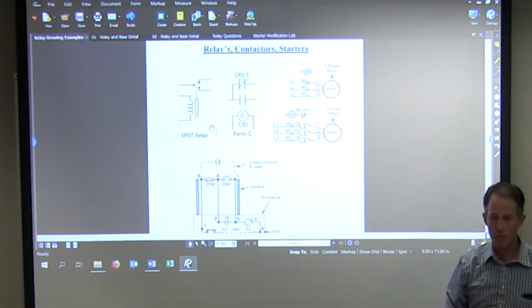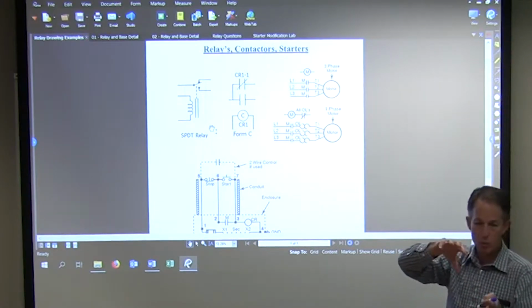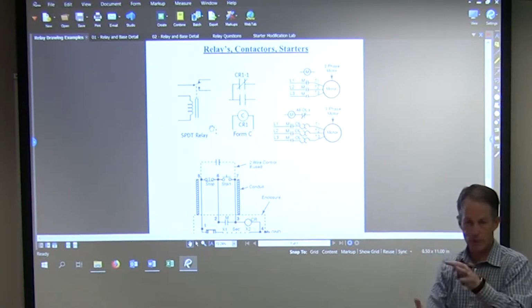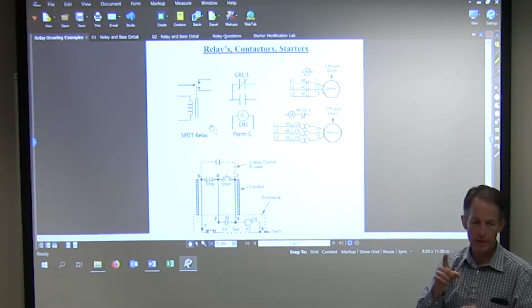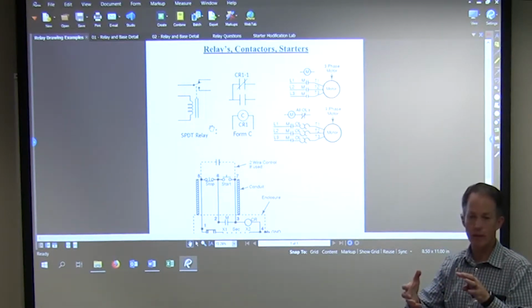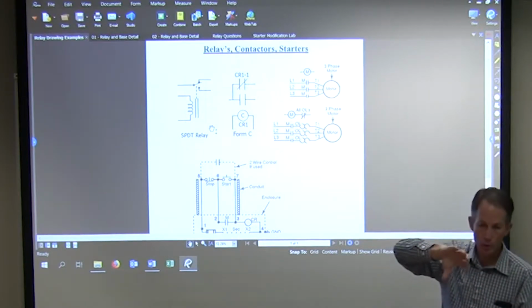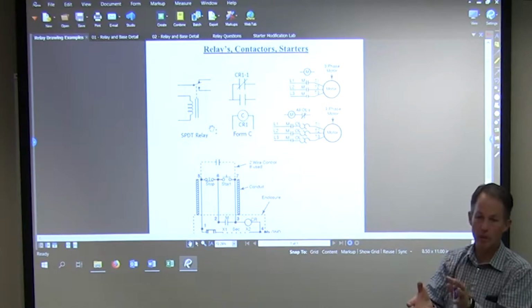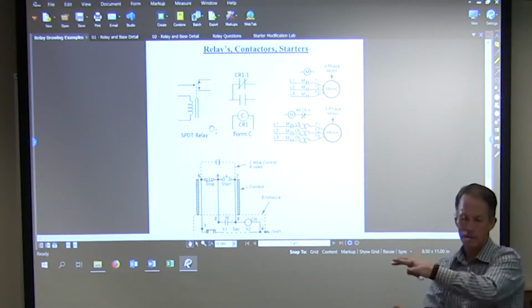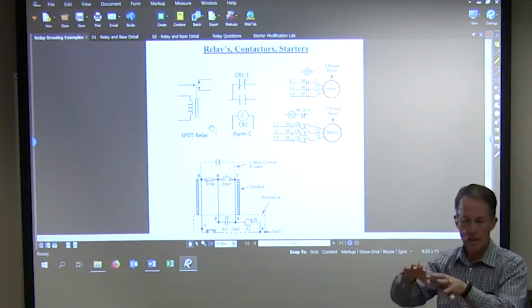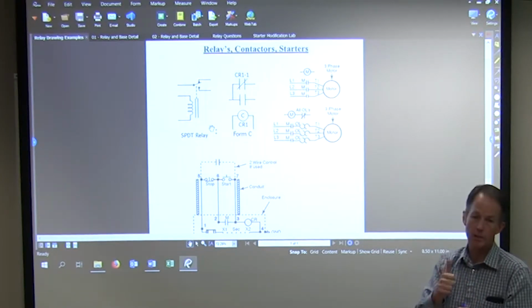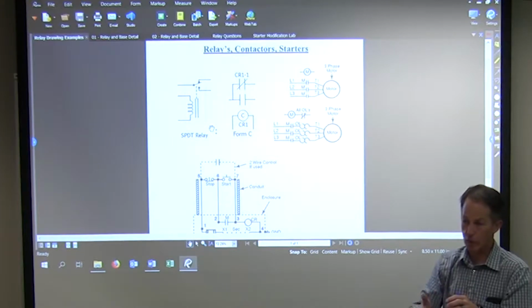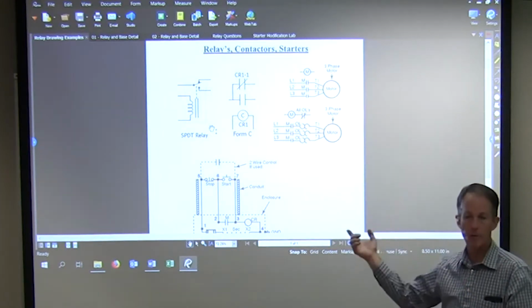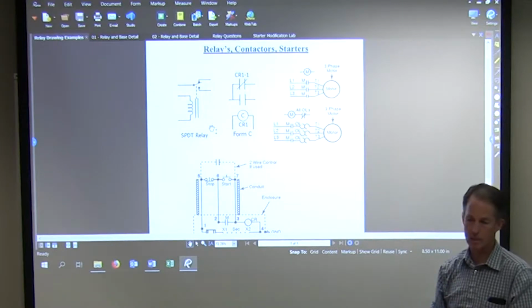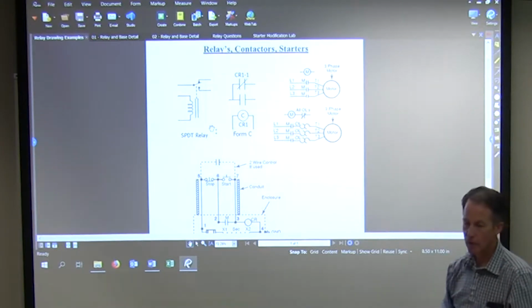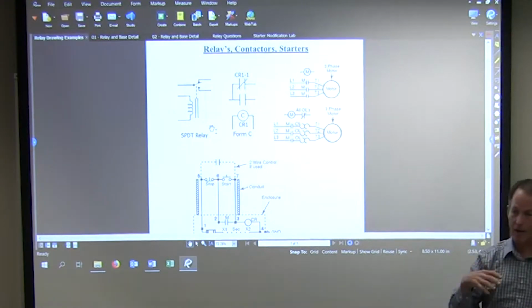When you single phase a motor, typically we have 3 phases working to turn this mass, and it takes a lot of power. If I only have 1 phase, the motor has what's called slip. In other words, it can't keep up. The rotating magnetic field gets ahead of the motor because it's heavier. I don't have all 3 sets of windings helping to keep it going. And as I get more slip, it increases the current draw. The current draw goes up and up and up, and eventually will burn up the set of windings of the one good phase that's left. So that's single phase in a motor, and that's why it's not ideal.